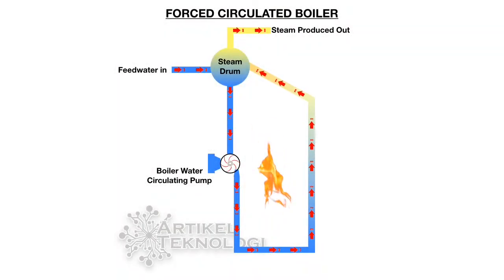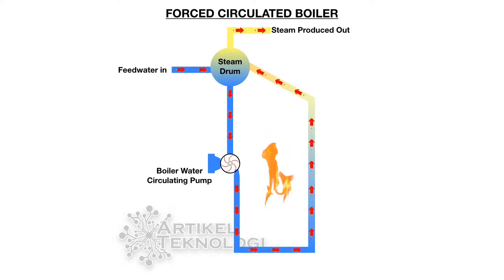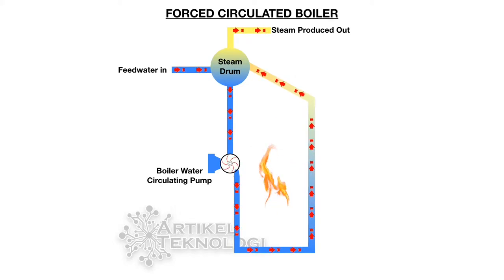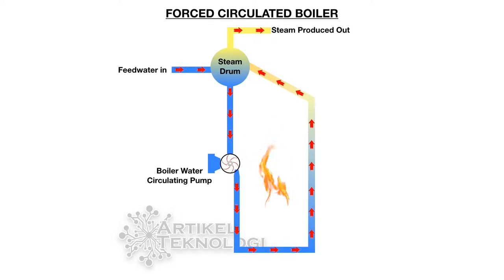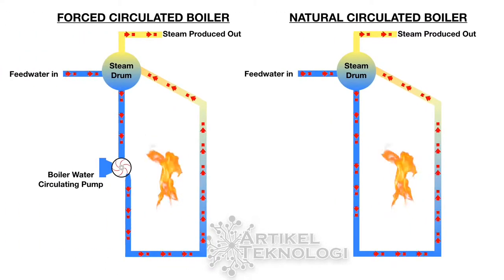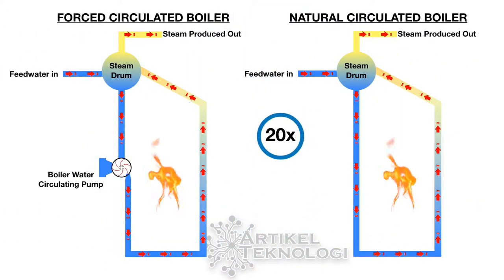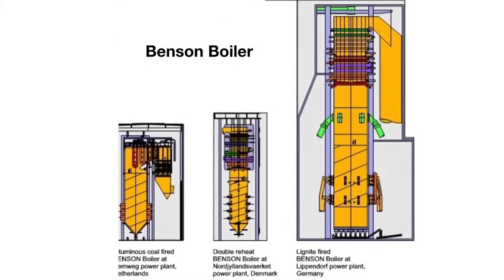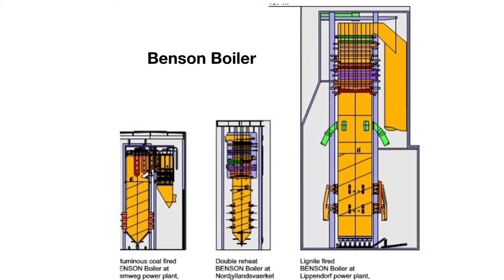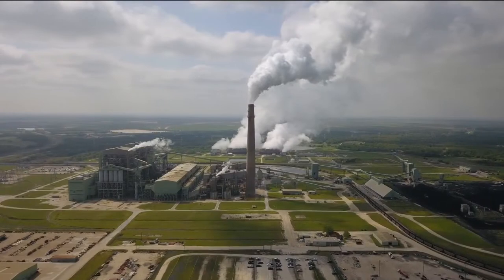Forced circulation boiler. Boilers with forced circulation use additional pumps to help the circulation of water. This type does not need to wait for water phase differentiation to circulate water. With external energy for the water circulation process, steam generation will not be limited by the size of the boiler. We can increase boiler capacity by only adding a circulating pump in the same boiler size. Forced circulation boilers can produce 20 times more steam than natural circulation boilers of the same volume. Examples include Benson boilers and Subcritical boilers.